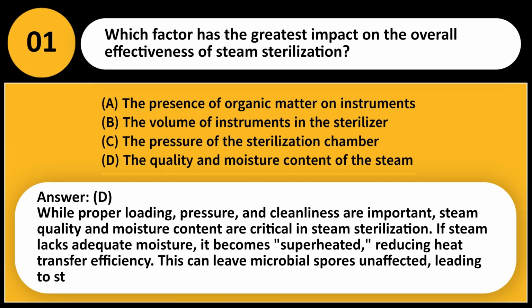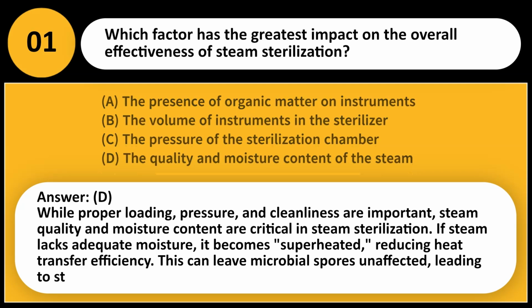Answer, D. While proper loading, pressure, and cleanliness are important, steam quality and moisture content are critical in steam sterilization. If steam lacks adequate moisture, it becomes superheated, reducing heat transfer efficiency. This can leave microbial spores unaffected, leading to sterilization failure.